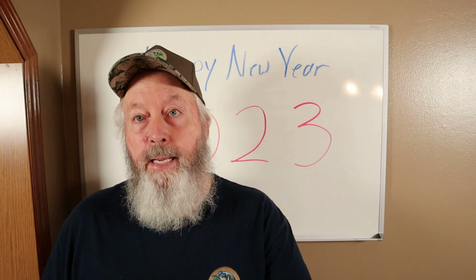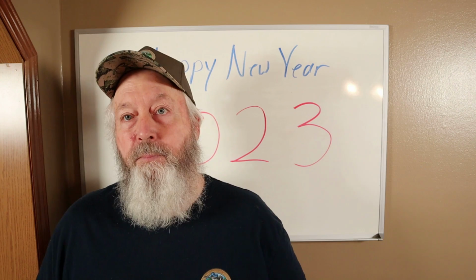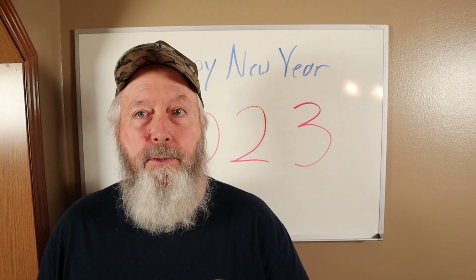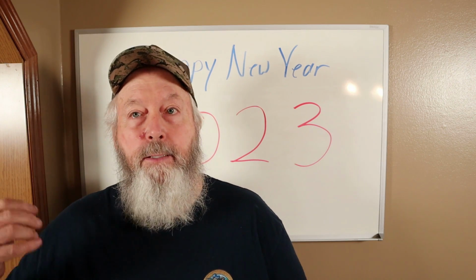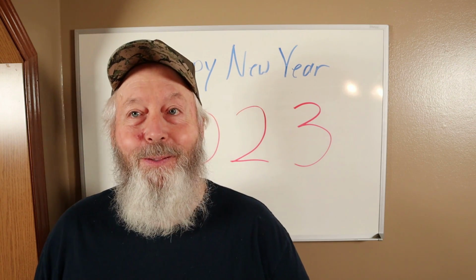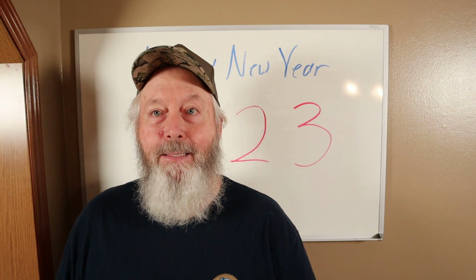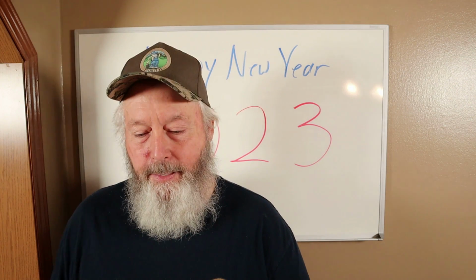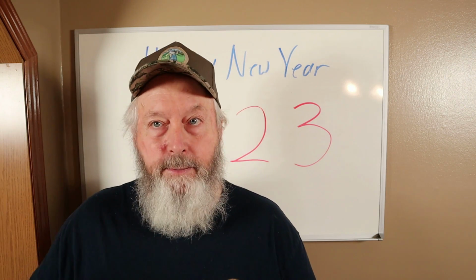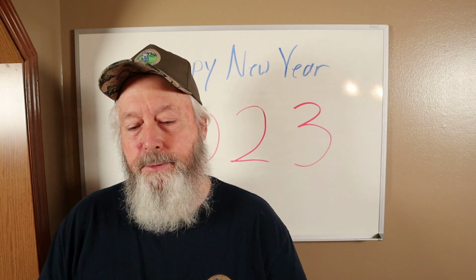Because the tank is producing between 100 and 200 psi. So you could imagine what would happen if you tried to hook an appliance up with no pressure regulator when it's supposed to have 0.4 to 0.5 psi, and all of a sudden it's got 100 to 200 psi. Not a good day for that appliance and probably whatever that appliance is installed inside of. So yes, that's why we have pressure regulators. It regulates the pressure down from tank pressure to a pressure that's usable by the appliances.